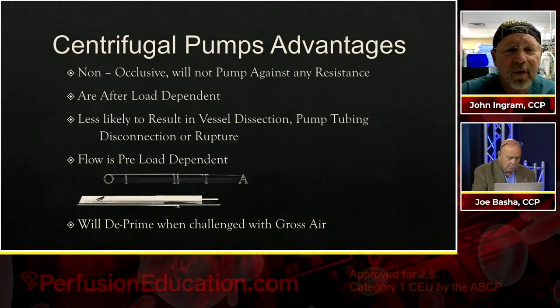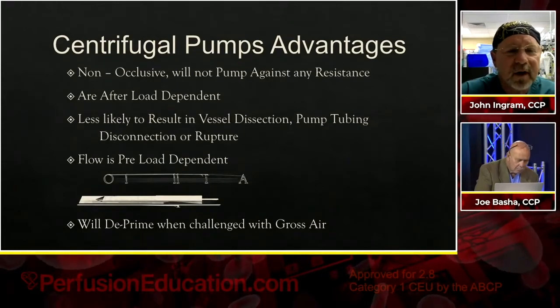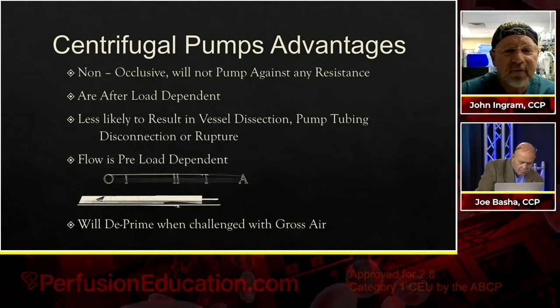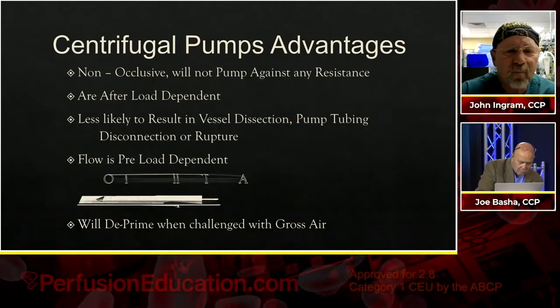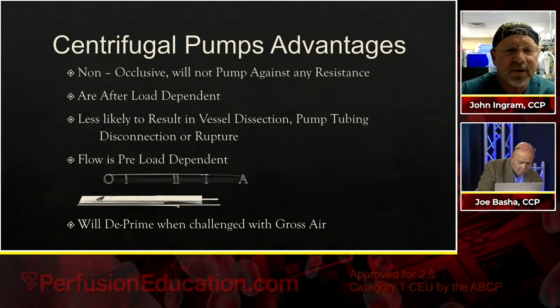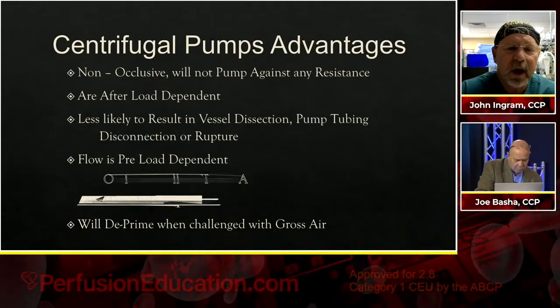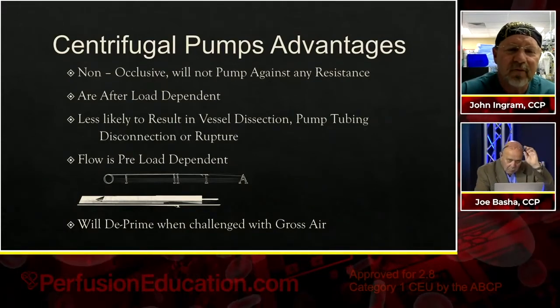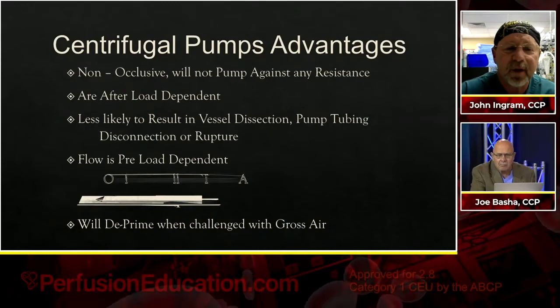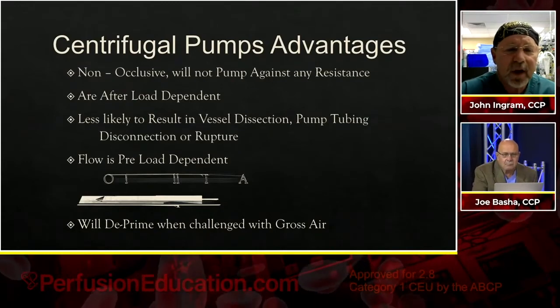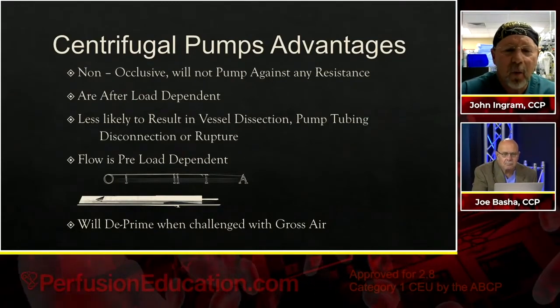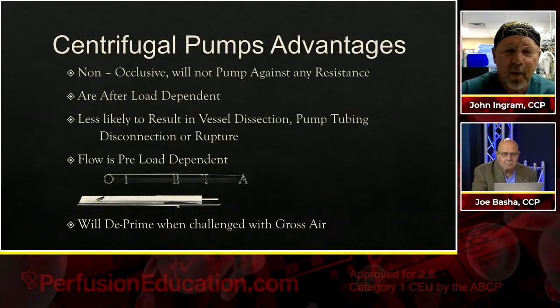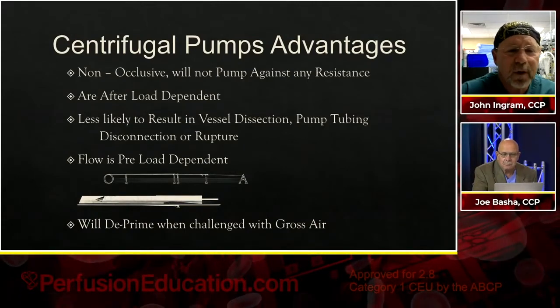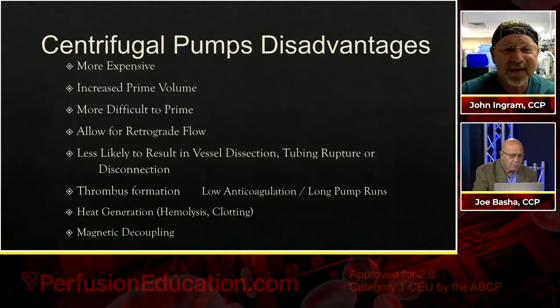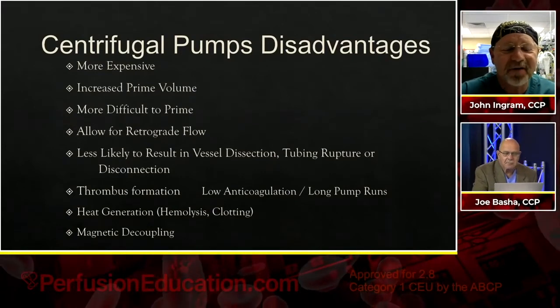I'm not sure what I'm looking at with that graphic there. What is that? So basically, if you have a centrifugal pump and you clamp or occlude the inflow line, it will also stop pumping, okay? It will also deprime when challenged with gross air, for the most part. I'm not sure what that graphic is there, Joe. That's some type of contamination on the download.